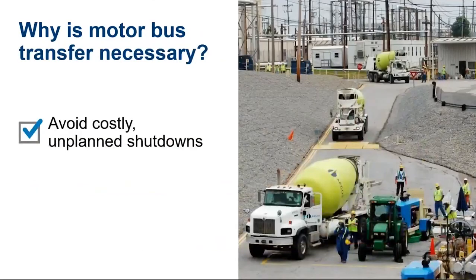Motor bus transfer is necessary when the loss of operation and processes results in substantial economical loss or environmental damage. A good example would be a cement processing plant. The moment the concrete stops flowing, it starts to harden. If the cement mixer stops turning, it does not take long for the mixture to solidify. And then you need to get the jackhammer to break down the concrete. This results in financial burden due to the downtime and also bringing in the additional personnel to fix the issue.